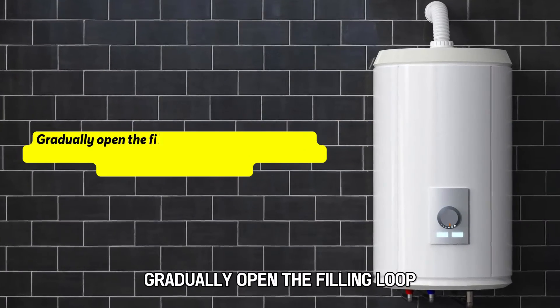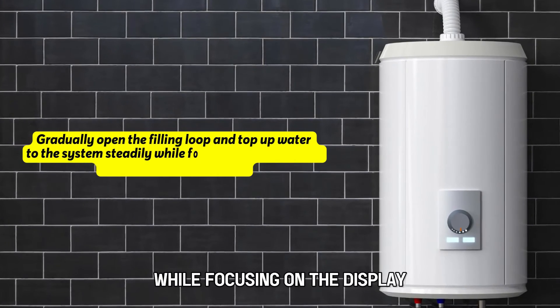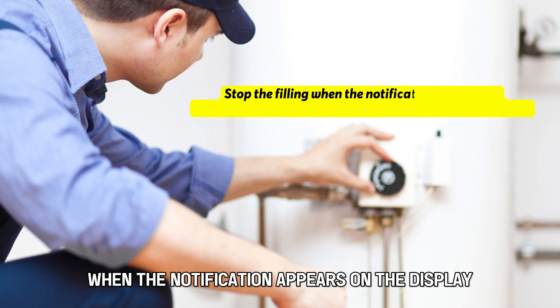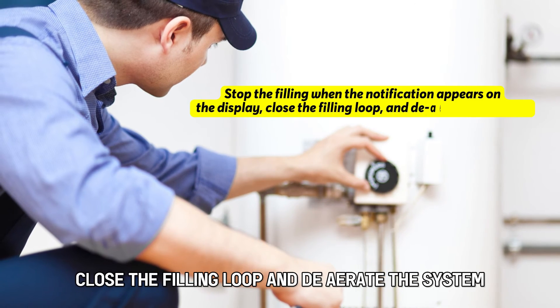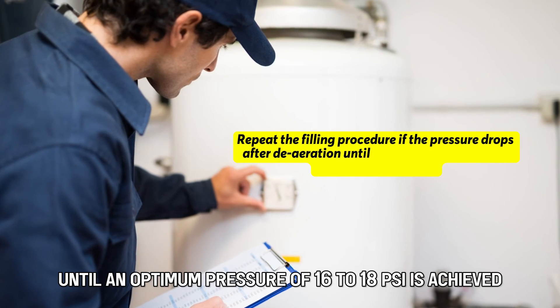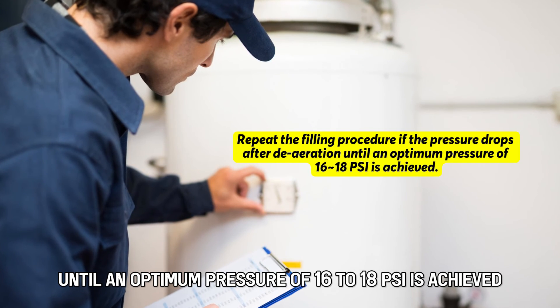Gradually open the filling loop and top up water to the system steadily while focusing on the display for the stop notification. Stop the filling when the notification appears on the display. Close the filling loop and de-aerate the system. Repeat the filling procedure if the pressure drops after de-aeration, until an optimum pressure of 16 to 18 psi is achieved.